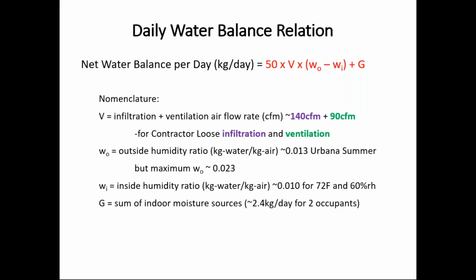So here's how we calculate the water balance. This is a simplified equation, but it's a very accurate equation. Multiply 50 times the infiltration ventilation flow rate. Multiply that times the water concentration or humidity ratio difference between the desired inside humidity ratio and the outside. In our case, 0.013 for the average Urbana outside humidity ratio and 0.01 for our inside. And then add the generation of moisture from humans breathing, cooking, washing, showering, and that activity.